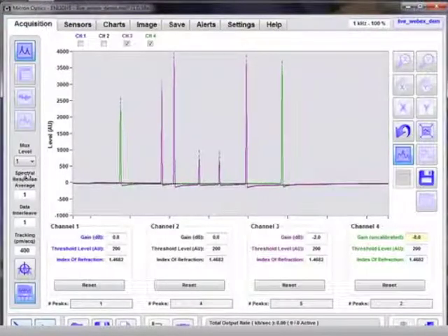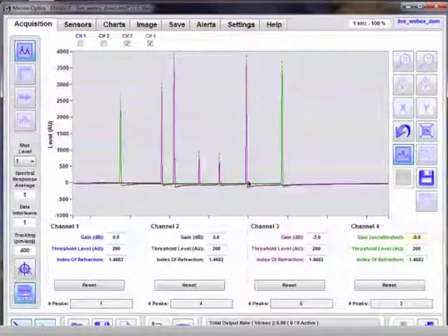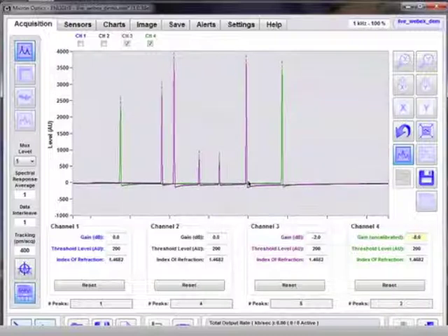you'll see there's an element here that says spectral response averaging. While this is of significant importance when using a static interrogator, an SM125 or any of the X25 line, its value for an X30 is only aesthetic. Essentially, this full spectrum trace for an SM130 is used for exactly how we used it, which is to establish gains, thresholds, and ensure that peak tracking is working as expected. There is no measurement data that's extracted from that full spectrum in the case of an SM130.